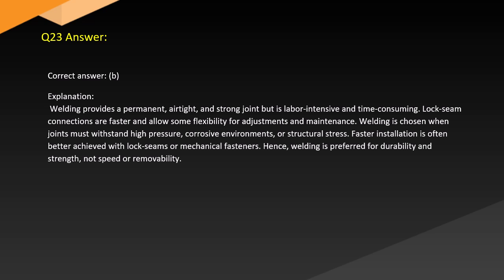Answer. Correct answer, B. Explanation. Welding provides a permanent, airtight, and strong joint but is labor-intensive and time-consuming. Lock-seam connections are faster and allow some flexibility for adjustments and maintenance. Welding is chosen when joints must withstand high-pressure, corrosive environments or structural stress. Faster installation is often better achieved with lock seams or mechanical fasteners. Hence, welding is preferred for durability and not speed or removability.